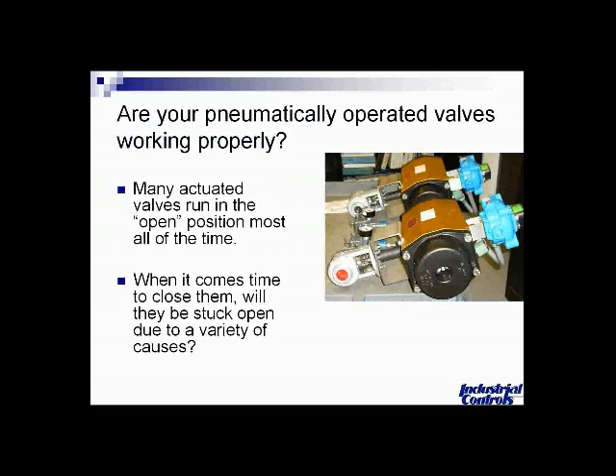process chemical plants out there whose key valves, either running steam or chemicals that are very expensive, are in the open position most of the time. And when it comes time to close those valves, that could be once every 6 months or once every 3 months, or in some cases it might just be for an emergency shutdown when you know that valve has to close.